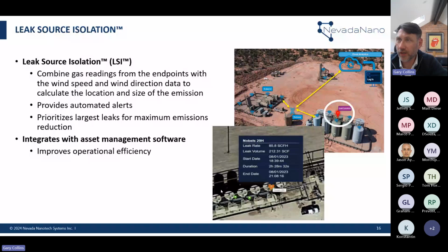So I've touched upon quantification, and I think it would be remiss of me not to highlight the addition of leak source isolation. This image in the top right shows a potential configuration. This is an upstream site, but you could have our system configured with a LoRa radio, with a gateway at a specific point connecting to your internet, or a cellular backhaul. Ultimately you'd have endpoints around the site, whether it's on tanks, a pump jack, or a separator. When a leak occurs, we have the ability to understand where that is.